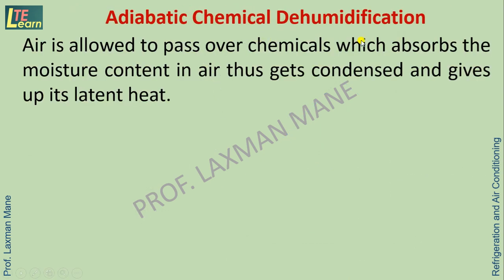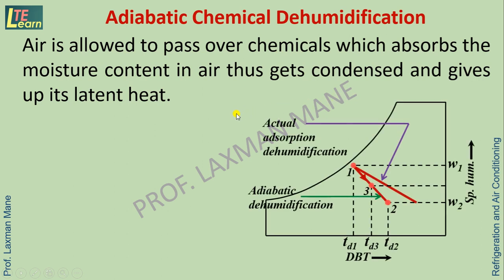Adiabatic chemical dehumidification: in this process, air is allowed to pass over chemicals which absorb the moisture content in the air. Thus the air is dehumidified and gives up its latent heat. This adiabatic chemical dehumidification process is shown on the psychrometric chart. The ideal adiabatic dehumidification follows path 1–3–2, while the actual adsorption dehumidification follows the line shown, where process 1–2 is the actual process.